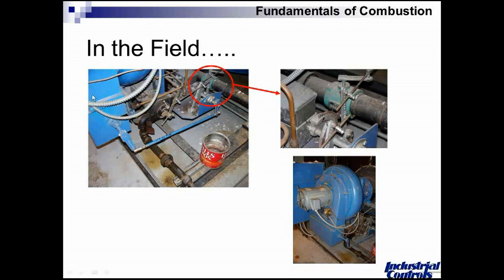The control characteristic of the damper, meaning its angular opening as a function of flow, is not terribly linear. A 10% change in rotation on the forced draft damper does not give us a 10% change in combustion air flow.